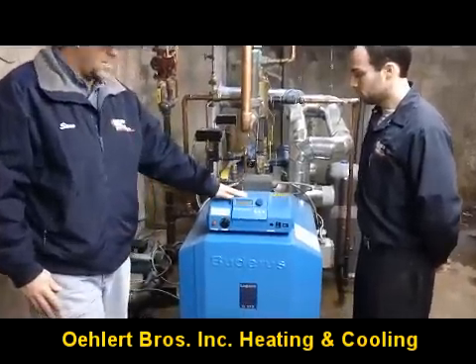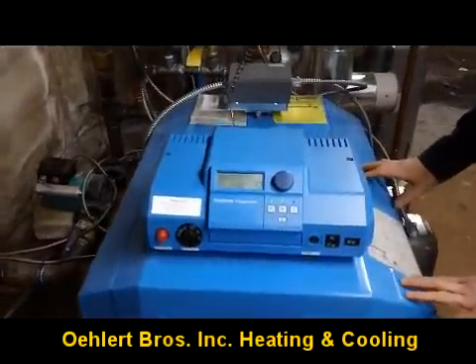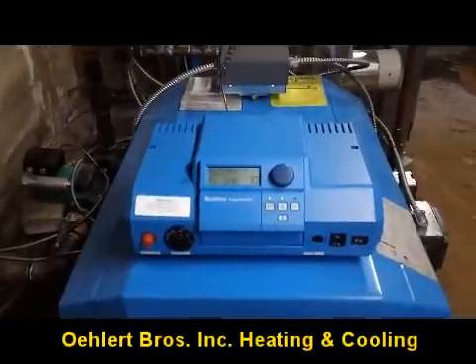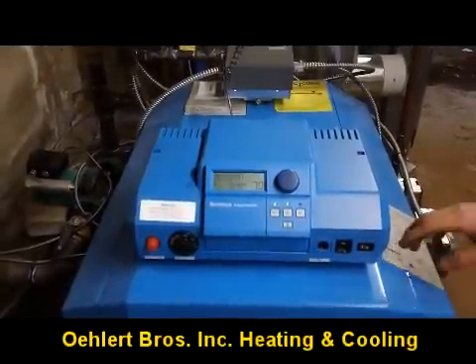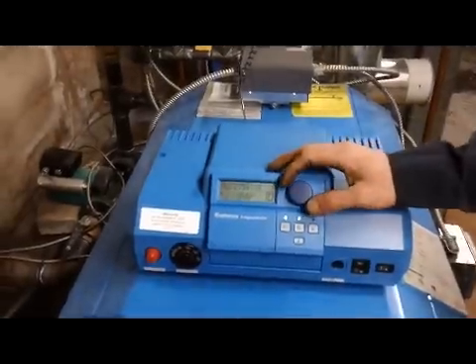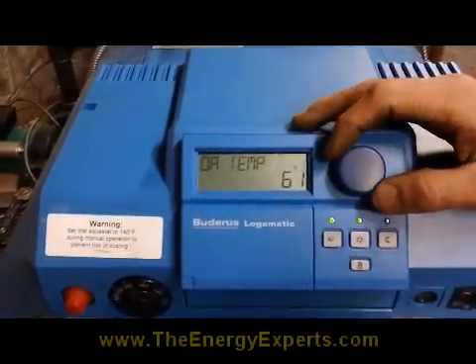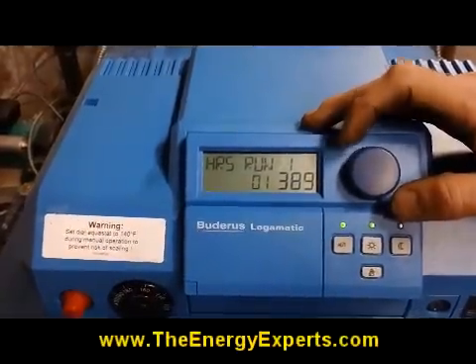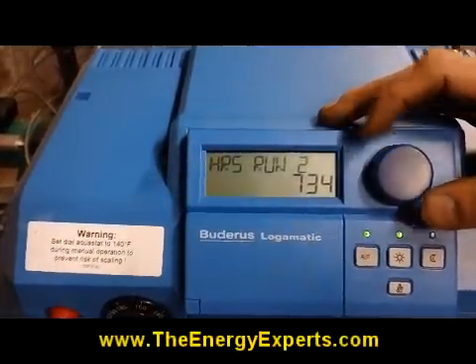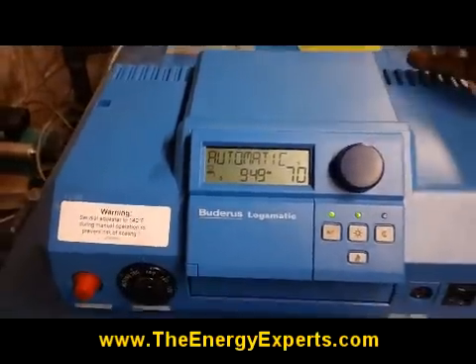This control here is the Logamatic control — pretty much the heart of the entire system. It takes your outdoor temperature readings, tells which boiler to fire up and when, and gives you displays of your boiler temperature, the outside temperature, and how long each boiler has been running. It's essentially like a programmable thermostat for a boiler.